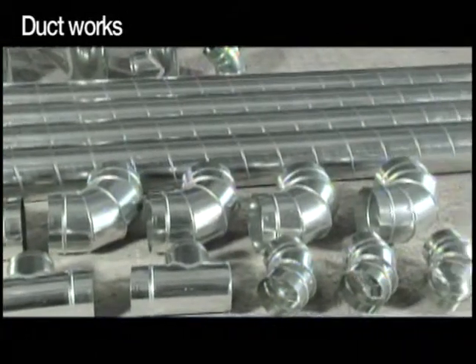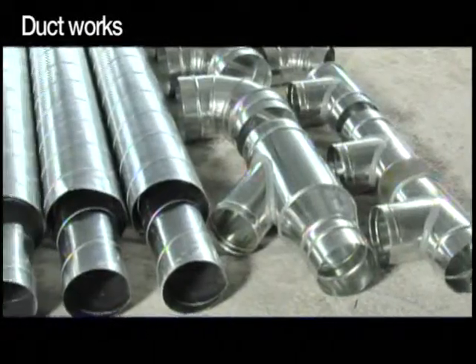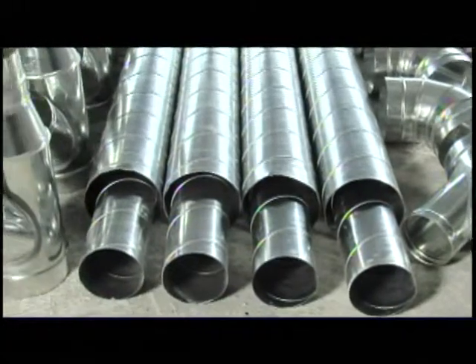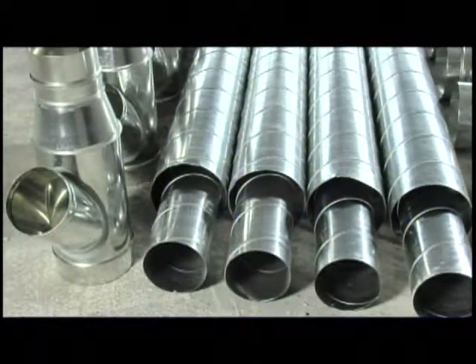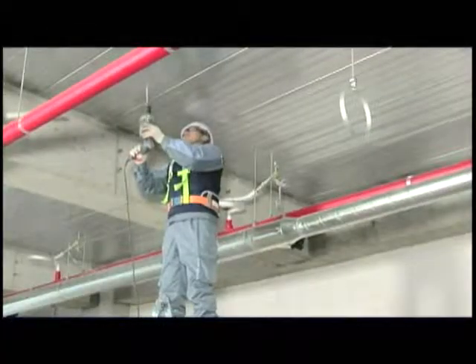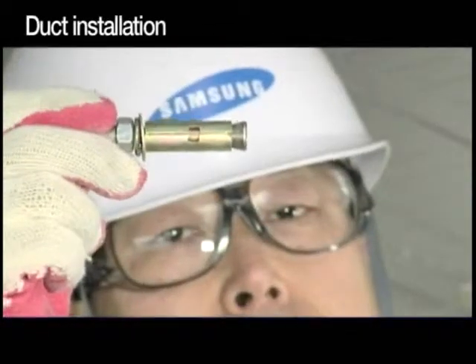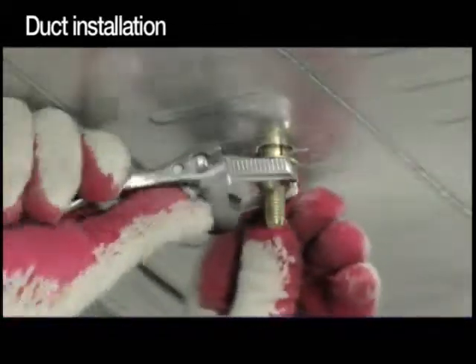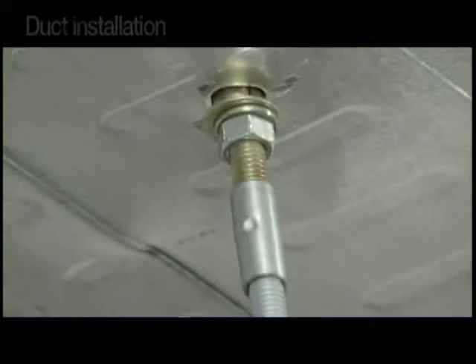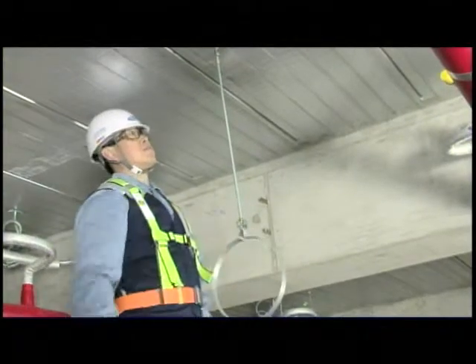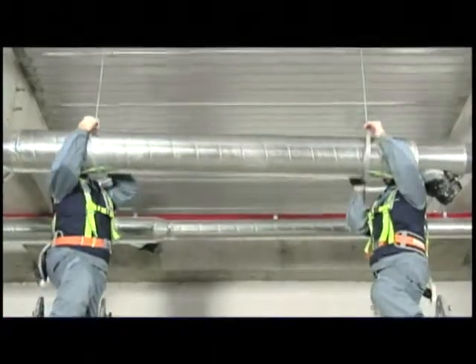Next, to install a duct, prepare the branch pipes and ducts according to the specifications in the drawing. Maintain the specified intervals when fixing the suspension bolts and install the hanger on the bolts and the duct on the hanger. The duct should be installed with the minimum distance. Excessive bending or sudden extension or shrinking should be avoided.